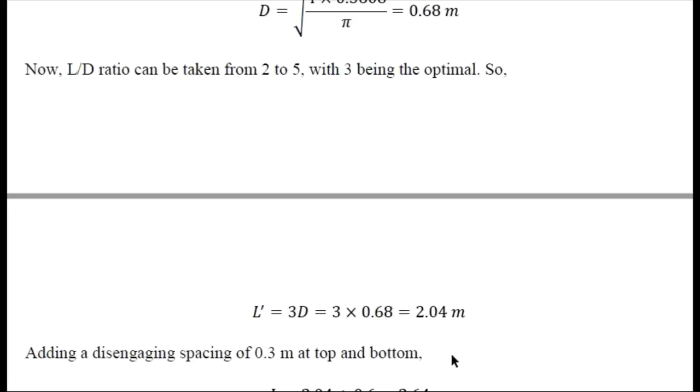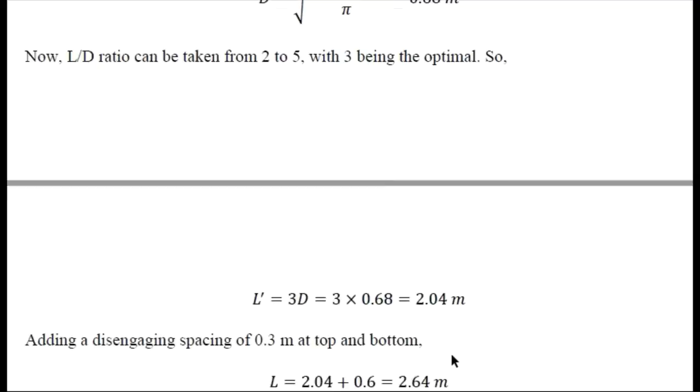Then we can add some space at the top and bottom as disengaging space where any carryover of the moisture can be taken backward. 0.3 meter is usual practice to add at top and bottom, so it becomes total height as 2.64 meter.